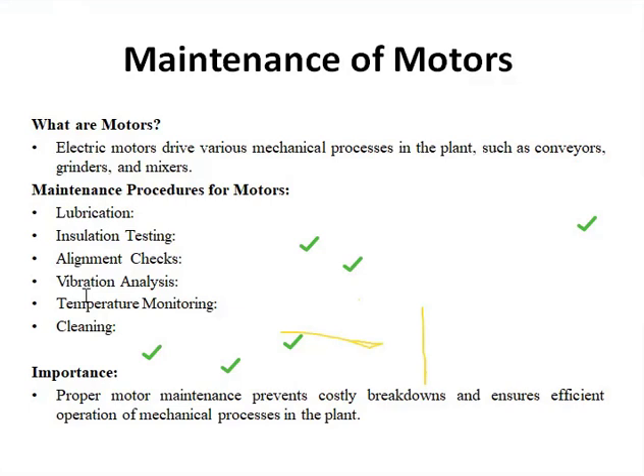Then we always do vibration analysis. High levels of vibration can signal issues like misaligned shafts or worn bearings. A motor driving big things, like hammer mills for example, may vibrate excessively due to bearing wear. So we always monitor their vibrations. If you see a motor vibrating abnormally, we always check for any problem. It could be the bearings having issues, maybe overload.